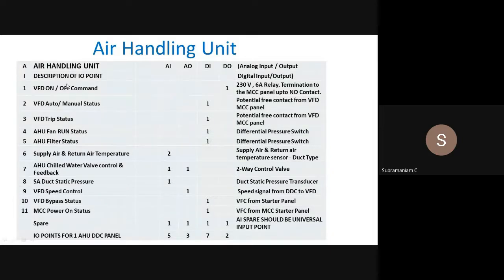Whatever I discussed earlier, you put these four things, AI, AO, DI, DO, in an Excel sheet. You put all the descriptions of the IO points, what all you want to do. Like I was telling you, if somebody says you are an operator in charge of the building, you have to switch on all the AHUs and control all. What I will do, first I will go and switch it on. Then I will put it in manual mode. Then if it is tripped, I will come to know.